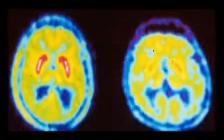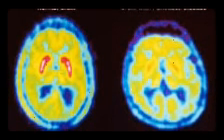Through differing thicknesses of tissue, the photons are attenuated differentially. The result is that structures deep in the body are reconstructed as having falsely low tracer uptake. Contemporary scanners can estimate attenuation using integrated X-ray CT equipment, in place of earlier equipment that offered a crude form of CT using a gamma ray, positron-emitting, source and the PET detectors.